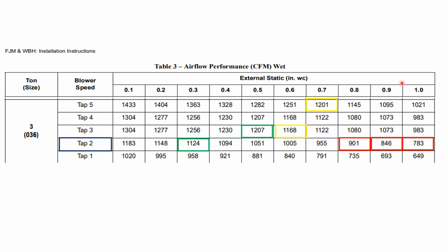a lot of homes were in this high static area because a return duct was too small or the return grill was too small. Those things have to be sized right, or you're going to have equipment that's up here in this danger area. Now, when we looked at this number a while ago, let's go back to the previous screen. If I can't get it to cooperate, we'll stay where we're at. 1115 was the number we needed.